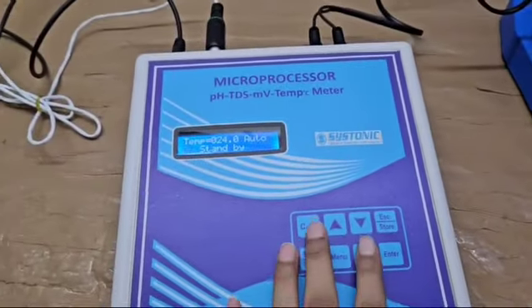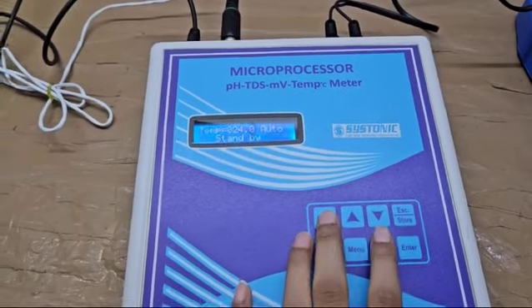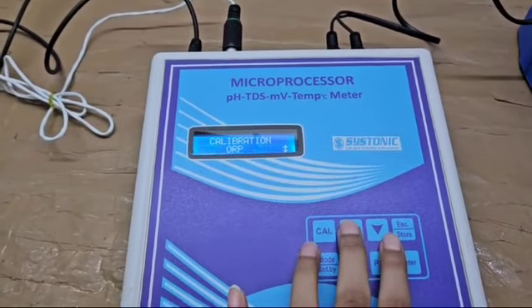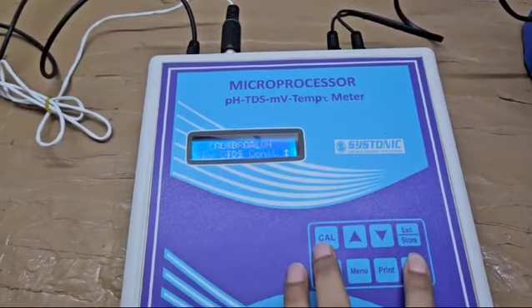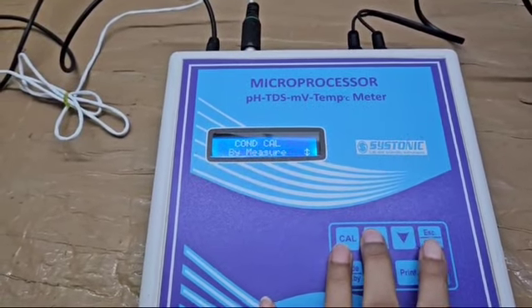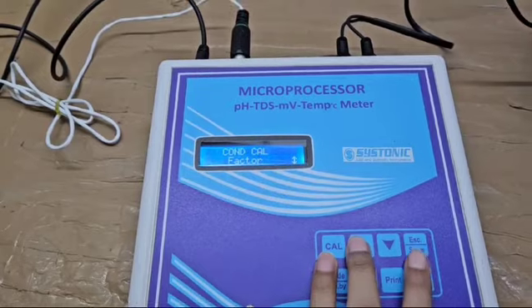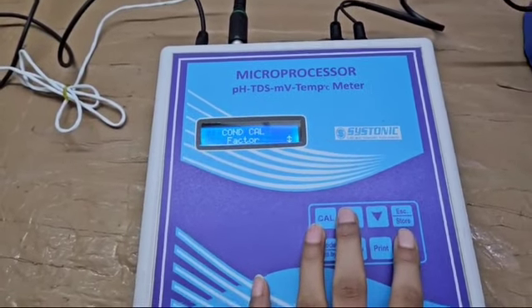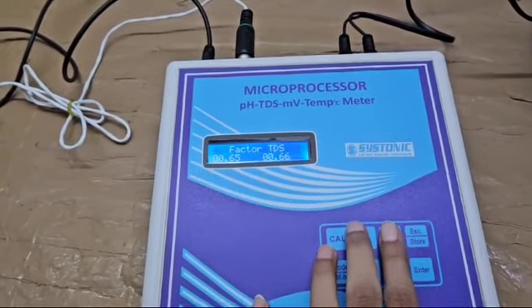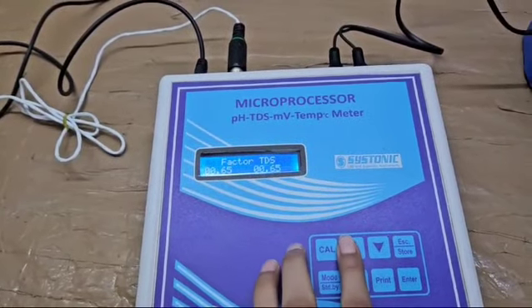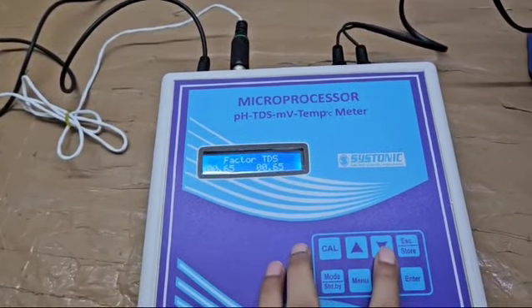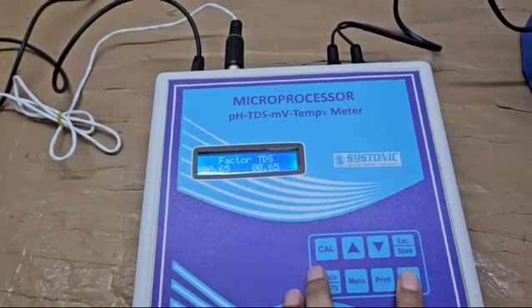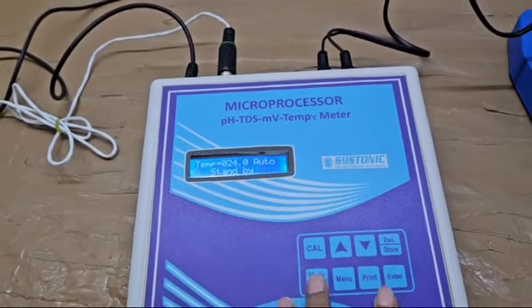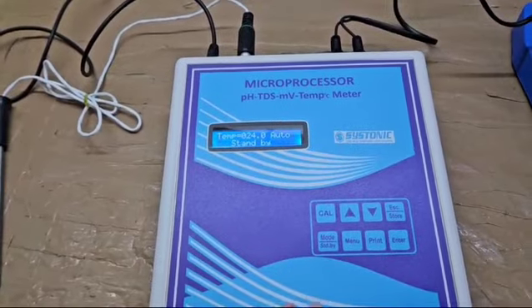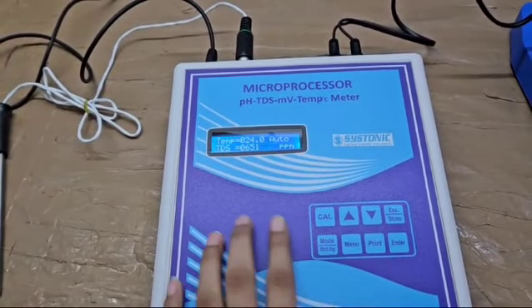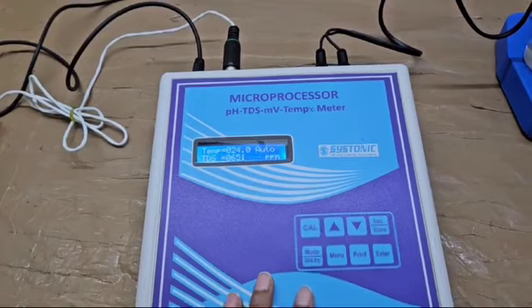So after that, we'll go to Cal, into TDS, press enter, and then we'll go to its factor, which is 65. If it's not put in there, you can change it through this up and down key, and after that press enter, and then we'll go to mode, and from here you can check the value.